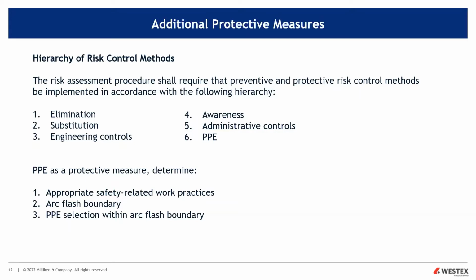Obviously, elimination is preventative, shutting it down, putting it in an electrically safe work condition. Administrative controls, preventative. PPE, certainly considered a protective measure. If it's worn, it will protect. But I'm going to talk a little bit later about maybe looking at PPE, especially a daily wear program, as being a preventative risk control method as well. So again, PPE is usually thought of as a protective measure. And of course, when you're in the arc flash boundary, you have to have it on. Outside, you don't. And of course, when you're in the boundary, you've got to make sure that it has the appropriate arc rating. And of course, you have to use appropriate safety-related work practices while in the boundary. You can't think you're bulletproof and get sloppy in there. You need to make sure that you're following the correct procedures with the PPE on. And of course, I think what we see out there most of the time, if they've taken the time to have the PPE on, they're going to be focused, and they're going to be utilizing the appropriate safety-related work practices.